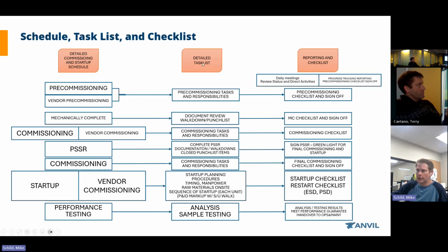And on each one of these, we have the detailed task list. We're defining who's doing that, and exactly when, and how long it's going to take. And then again, we're back checking and we have checklists. So we're doing progress tracking. We've got to track everything. Loop checks are always the critical path. I want a daily report on where we're at on loop checks. If I have 1,000 pieces of instruments, 1,000 loop checks that have to be done, and we need to get this done in 2 weeks, I need a daily report on where we're at. I need to know what instruments failed, what needs to be replaced. Do I have a bad transmitter?